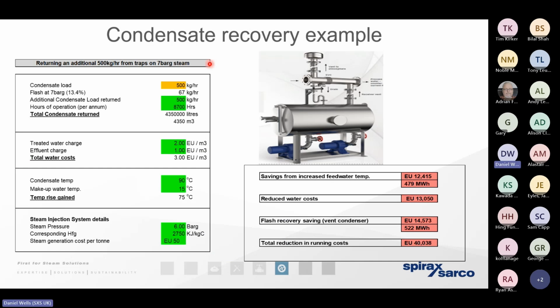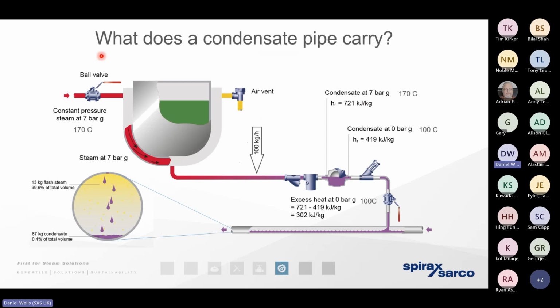So, as we mentioned, if we've got all the variables in calculating the cost of steam, the same variables apply with calculating the benefit in increasing the mass of condensate we can now bring back from the various processes around site back to the boiler house. We need to understand that when steam gives up its heat energy and condenses, its useful heat energy goes into the process, and the byproduct that is left behind is going to be a single phase liquid at the same pressure and at the same temperature as the steam, at least until it depressurizes when it moves across the trap.